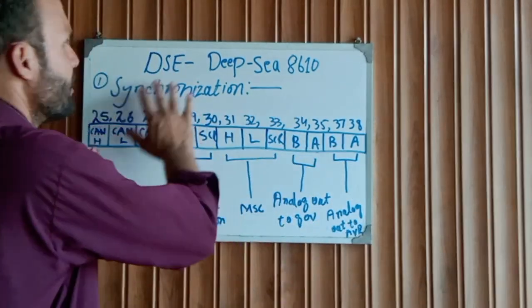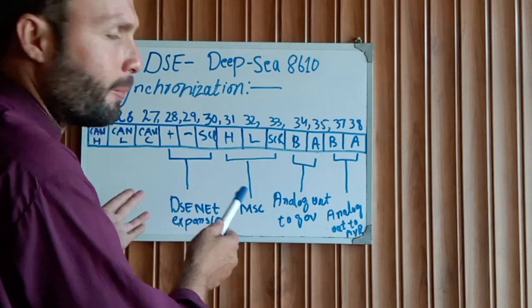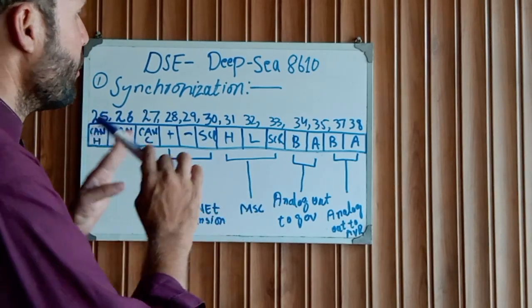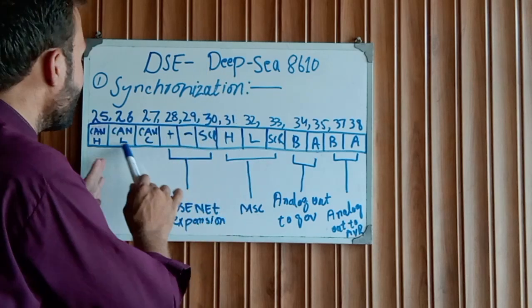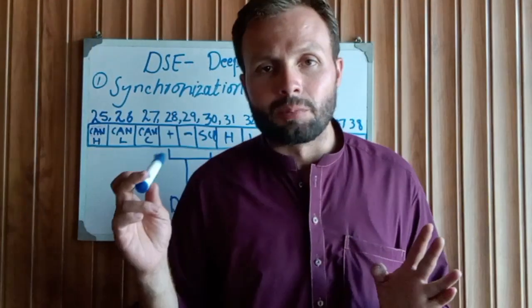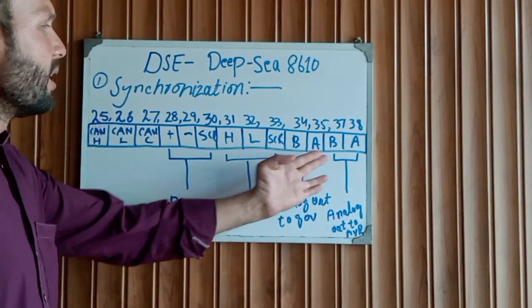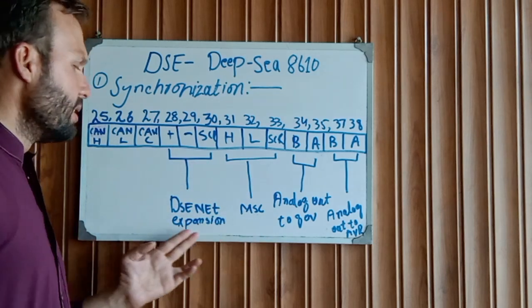After this, DSE controller is used for the power supply of the controller - the three-phase with neutral voltage input, CT connection input, and MPU connection input. Another connection is not really very tough, but some electrician and generator technician brothers are confused to install this synchronization module and don't understand the connection of the governor, AVR, MSC, and DSE net expansion. Let's get started to explain each pin. As you can see, I already drew the diagram and table.